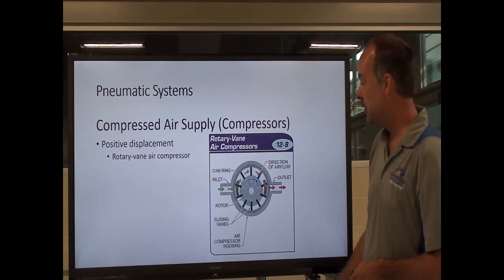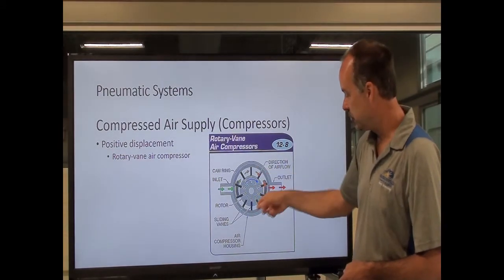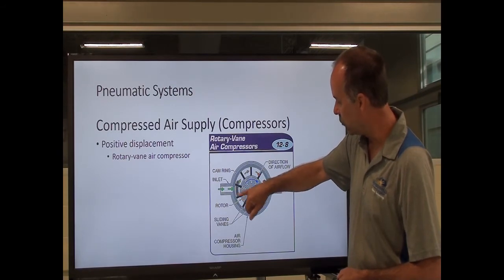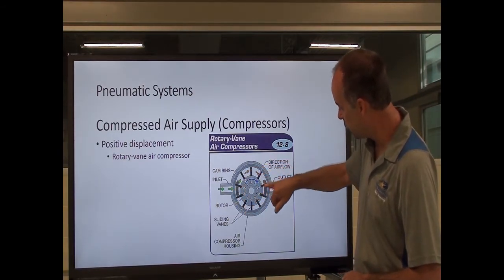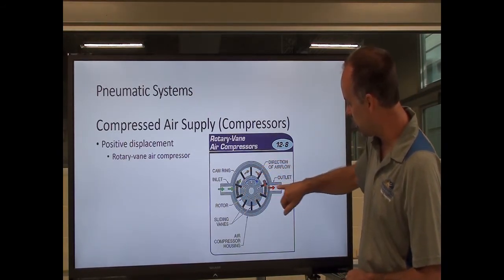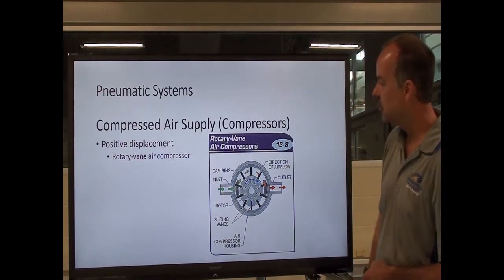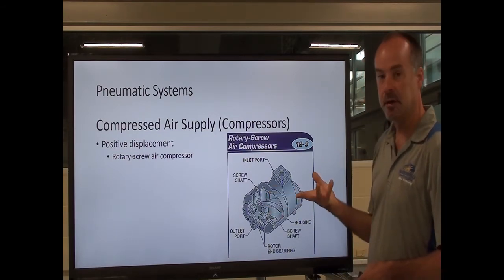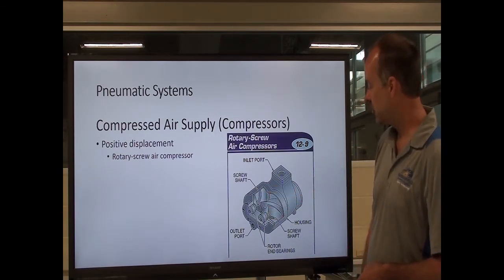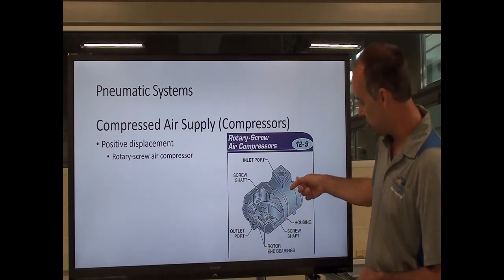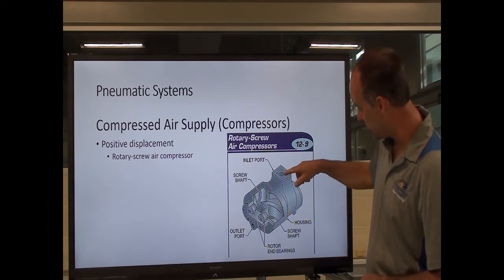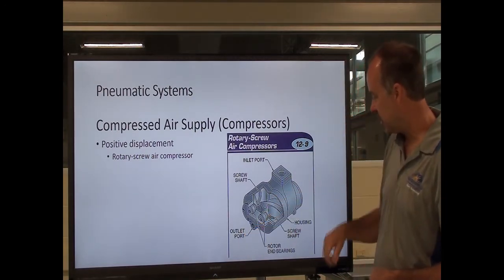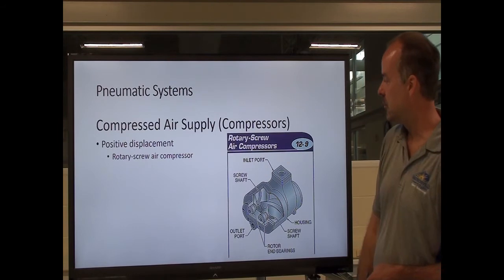A rotary vane air compressor — much like a vane hydraulic pump, it's the same principle. We have a spinning hub with our vanes; we draw air in and as it spins around to our outlet, we're compressing it and sending it out to our receiver. The rotary screw type is kind of like a gear pump in hydraulics, but it uses two spinning screws that actually draw air in and compress it — air comes in here, gets compressed, and comes out here. Just another form of air compressor.